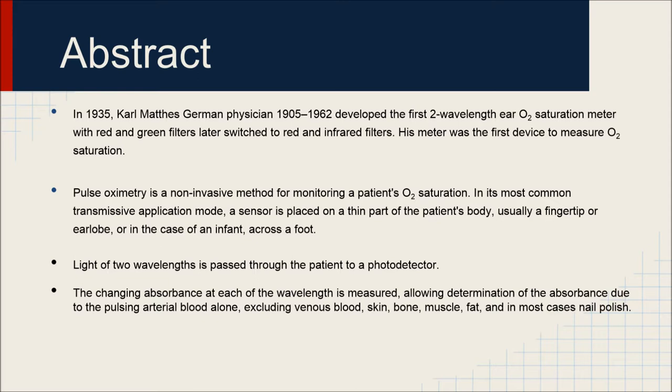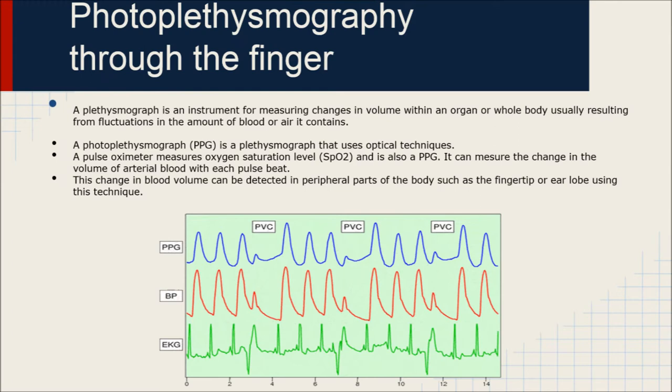Light of two wavelengths is passed through the patient to a photodetector. The changing absorbance at each of the wavelengths is measured, allowing determination of the absorbance due to the pulsing arterial blood alone, excluding venous blood, skin, bone, muscle, fat, and in most cases, nail polish.